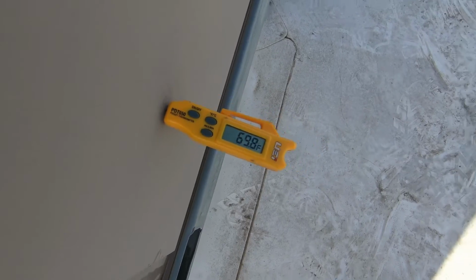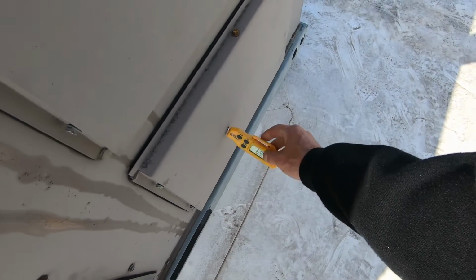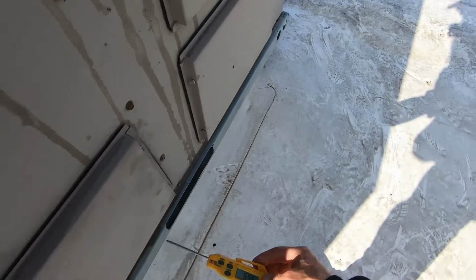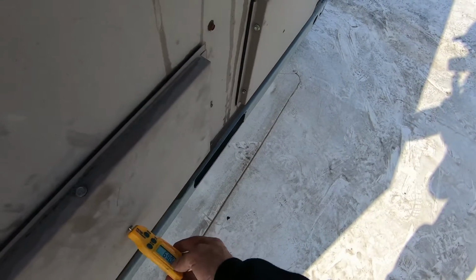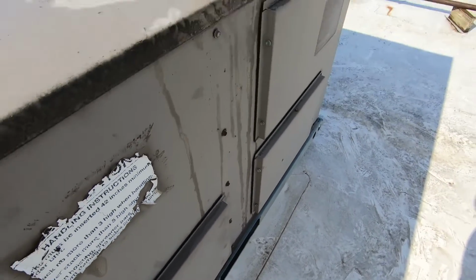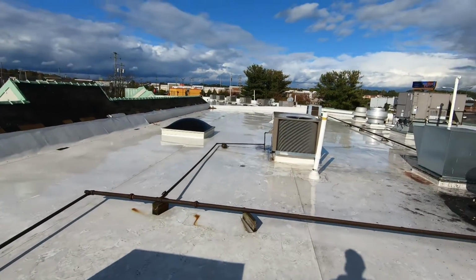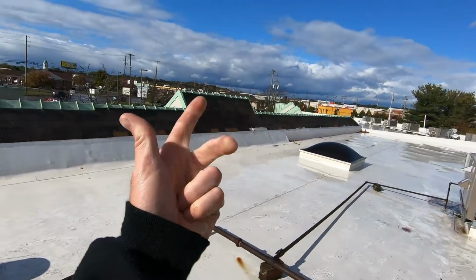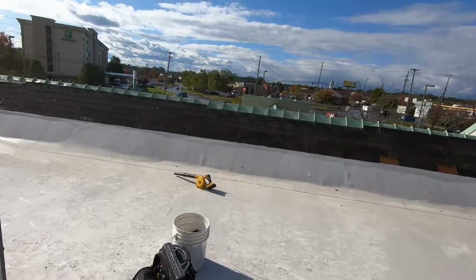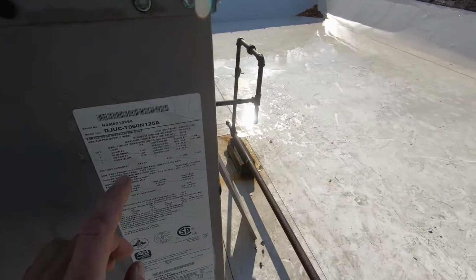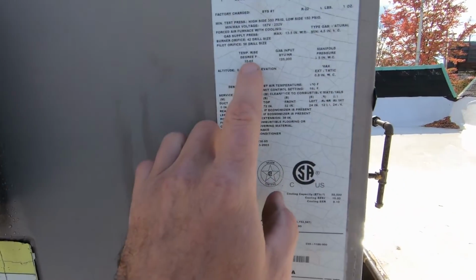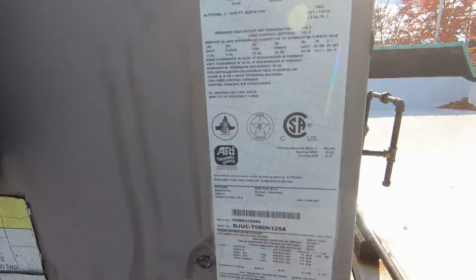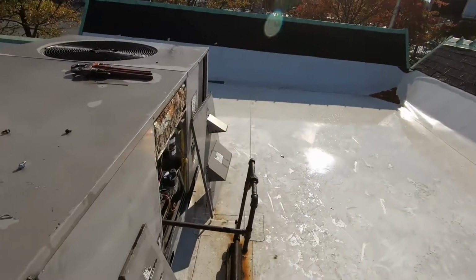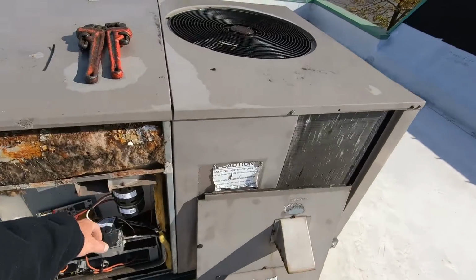It's like 69 degrees, which is about right because we were reading about 67, 66 in there. And last I saw here, we were at 110. So let's call that 70, 80, 90, 100, and 110. That's 40 degree temp rise. I can't imagine it's gonna get much more than that. I think we're gonna fall right in line with our temp rise.